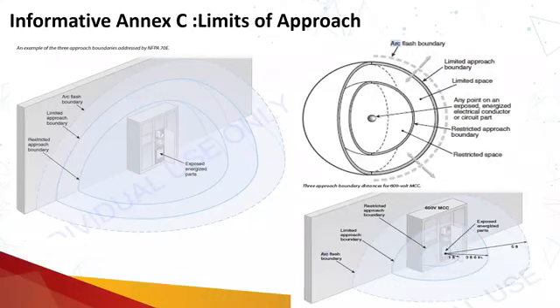So at this point, just keep in mind that the shock protection boundary is independent of the arc flash boundary, and the arc flash boundary is independent of the shock protection boundary. For example, 70E says that if you are working on a system operating at 50 volts, the shock hazard exists. If you are working on a system where the incident energy is 1.2 cal per centimeter square, the arc flash hazard exists. So there could be scenarios in which I'm working at 50 volts, so the shock hazard exists, but the incident energy is not greater than 1.2 cal per centimeter square, so the arc flash hazard does not exist. Once the arc flash hazard does not exist, the arc flash boundary is also not there. So in this scenario, the shock protection boundary exists, but the arc flash boundary does not exist.